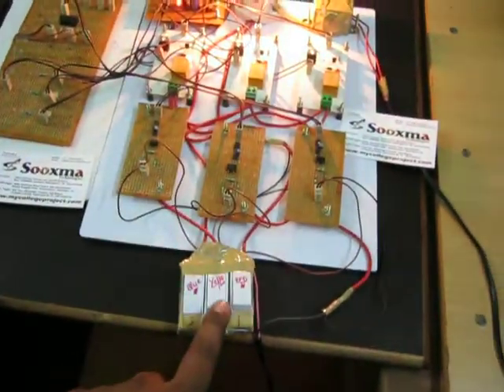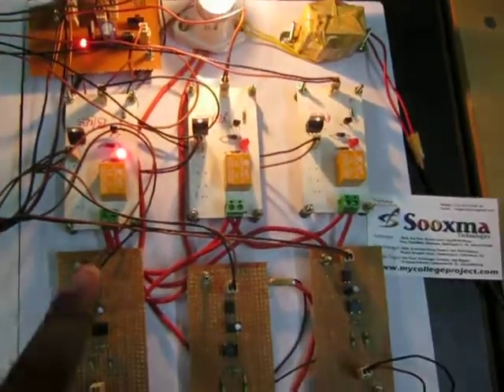When I turn on the yellow, there is a preference. First preference is going to be the red phase, then yellow, then blue. Initially I turned on the blue and now the yellow. Without disconnecting the load, the yellow relay will be on and the yellow supply will be given to the load.